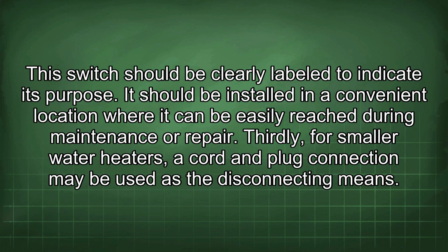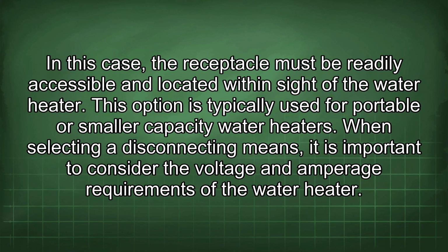Thirdly, for smaller water heaters, a cord and plug connection may be used as the disconnecting means. In this case, the receptacle must be readily accessible and located within sight of the water heater. This option is typically used for portable or smaller capacity water heaters.